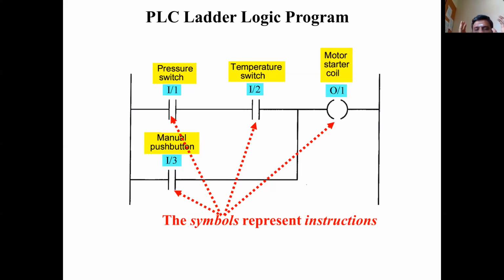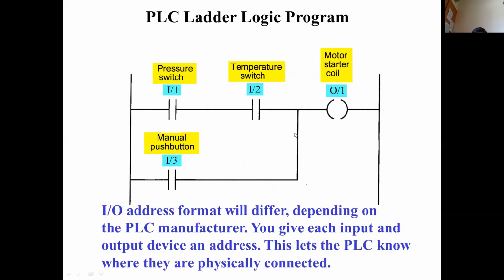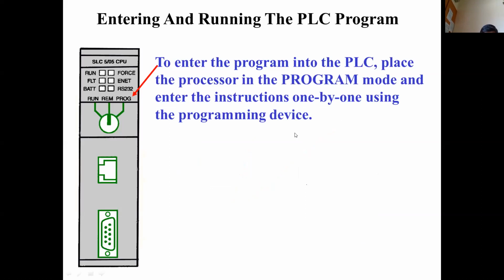So the main things we use in a PLC program are NC, NO, and the output coil. This is a normally open contact, and this is the output coil. And one more is the NC, that is, it will be closed. This is your normally closed contact.